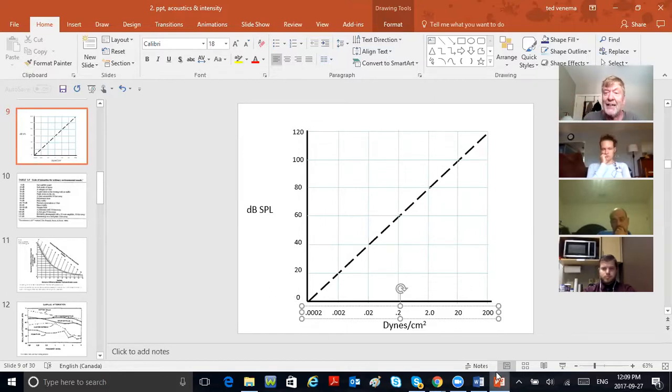The gain is represented as simple dB, not dB SPL, just dB. And the sum of input dB SPL, the sound coming into the mic, plus the lift or amplification in gain, dB alone, equals the sum total output that's hitting your eardrum.